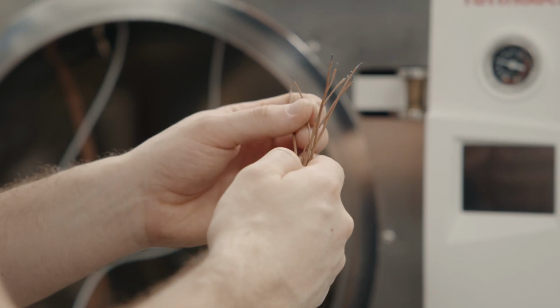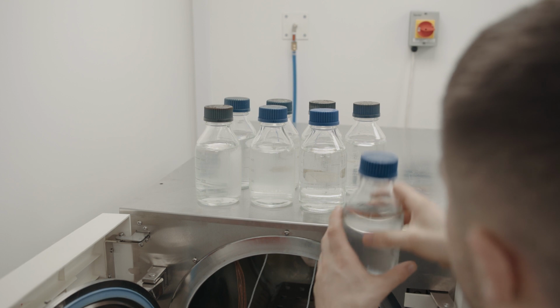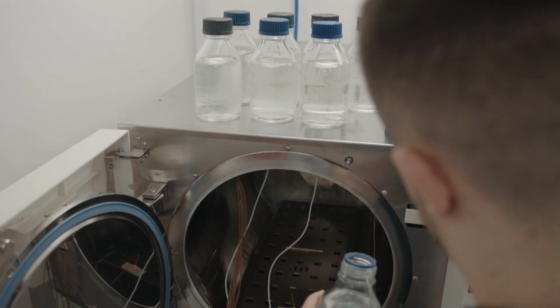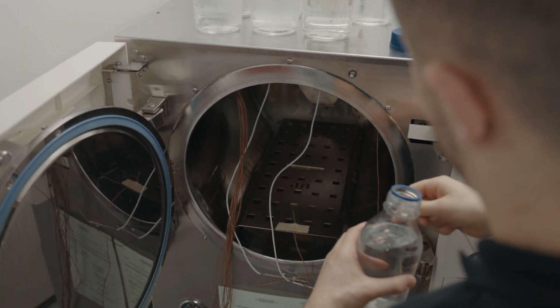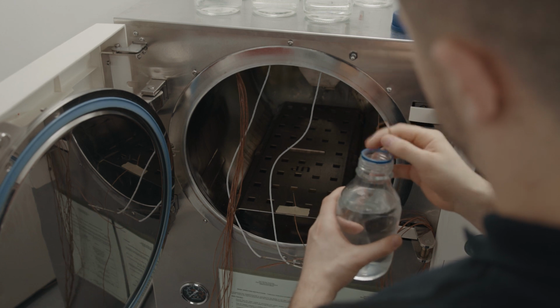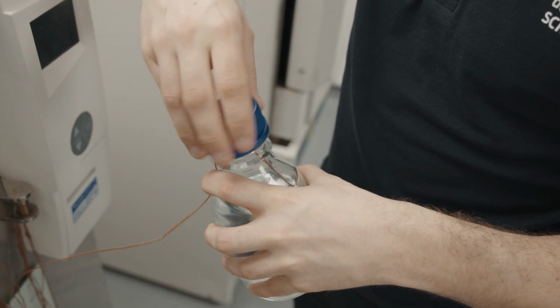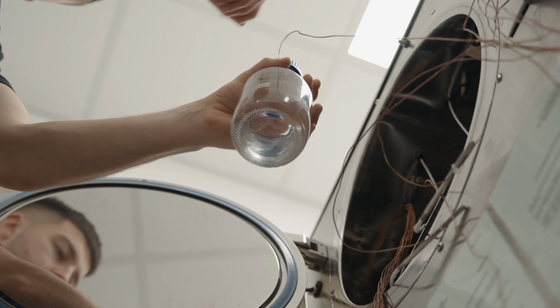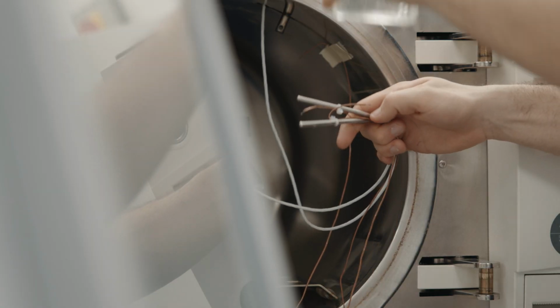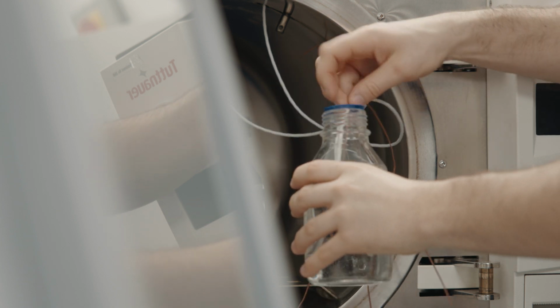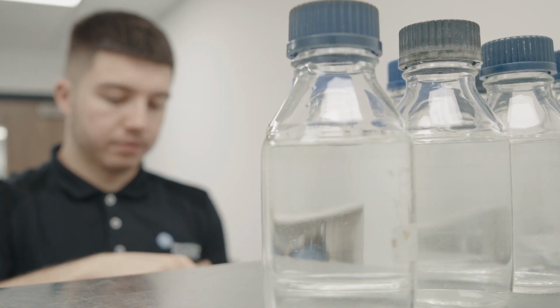To validate, a representative load is required. Not necessarily media, but water can be used for liquid cycles. As with calibration, 6 thermocouples are placed within the autoclave chamber. A further 6 are placed within different parts of the load to be validated. The function of these additional thermocouples is to monitor the temperatures achieved throughout the cycle.